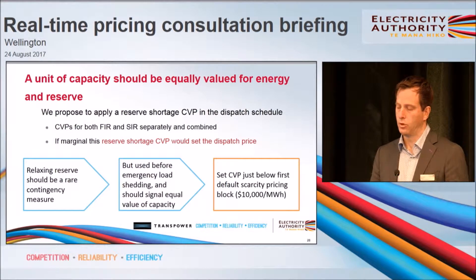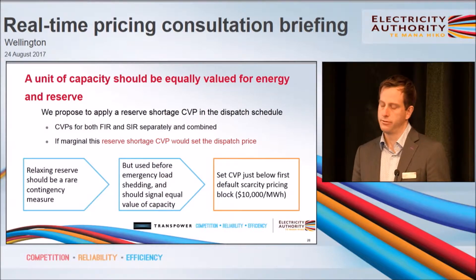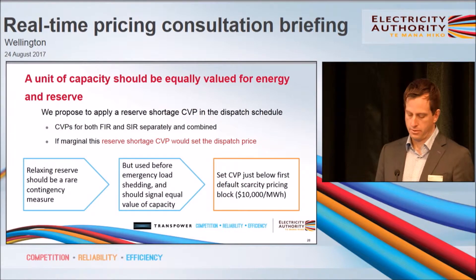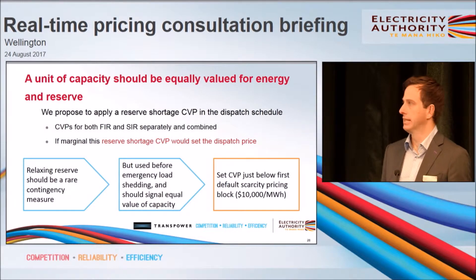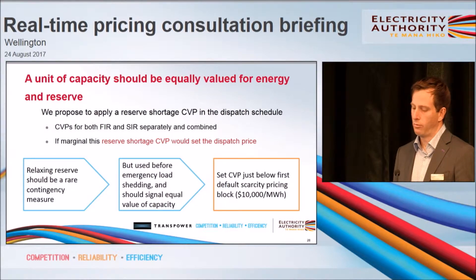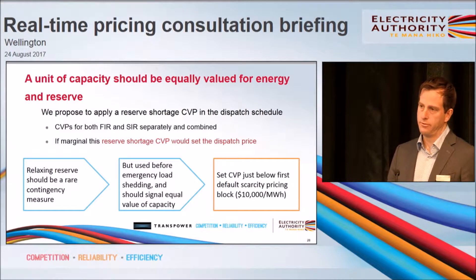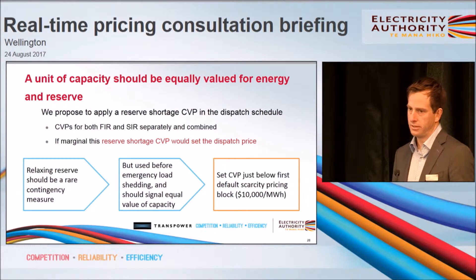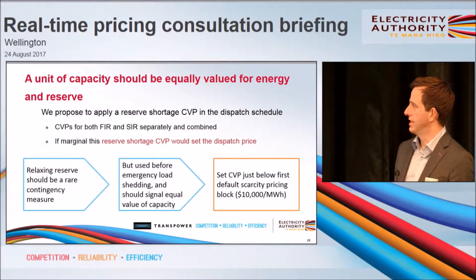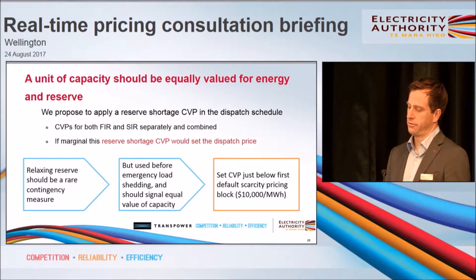We have done some modelling work, but at this point we haven't set forward specific proposed values, and we'd be keen to hear your thoughts on how that should work and what sort of considerations should be taken into account in any algorithm we would use to determine those values. The general logic is that relaxing reserve in this way should be rare — a rare contingency measure — but we should do this before we use instructed emergency load shedding, and when we do so we should signal that the value of that reserve being sacrificed for energy has equal value to a unit of capacity used for energy in the first place. Logically, the way to do that would be to set this reserve shortage CVP at some value just below the first default scarcity pricing block.